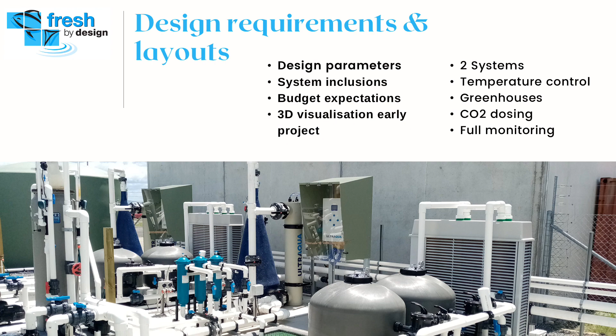CO2 dosing was included as part of the system, along with a full monitoring package and pump control. This included sensors for temperature, pH, salinity, oxygen, flow and pressure monitoring of the filters. We also included VSD control of the main pumps, which allowed perfect feedback of pump control.